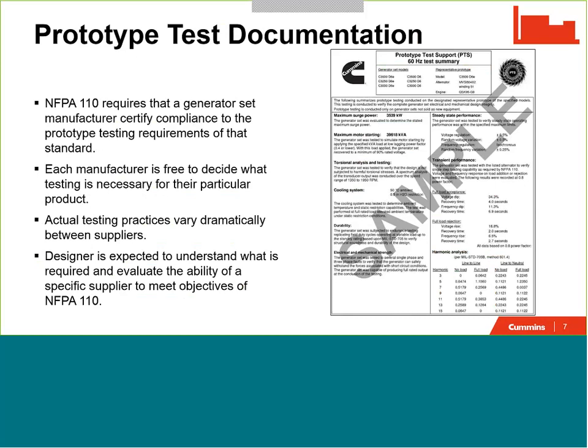So I'm going to talk here, again, first a little bit about NFPA 110 because most of you may have had the thought, when I said there's no one standard that specifies testing requirements for generator sets, well, how about NFPA 110? And NFPA 110 does do a pretty great job, actually, of listing, and I'll just stop at listing, some of the requirements for prototype testing.